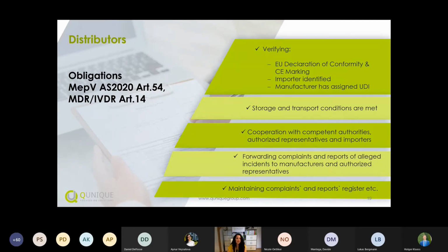The obligations of the distributor are to check the declaration of conformity, then check if the importer is identified, so if it's visible on the label, and if the manufacturer has assigned a UDI. Unfortunately, I still see many distributors who do not have the storage and transport conditions under control. So make sure that you really understand the conditions from your manufacturer and please implement them. As a distributor, you also need to cooperate with your competent authorities, of course, and with the authorized representative and importers. Here as well, you need to have a register of your complaints, and in case you have an incident report, you need to immediately forward it to the manufacturer and authorized representative.